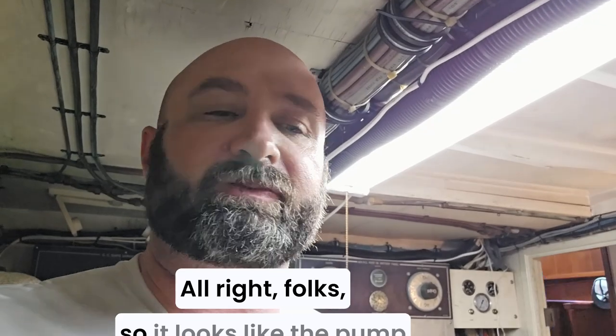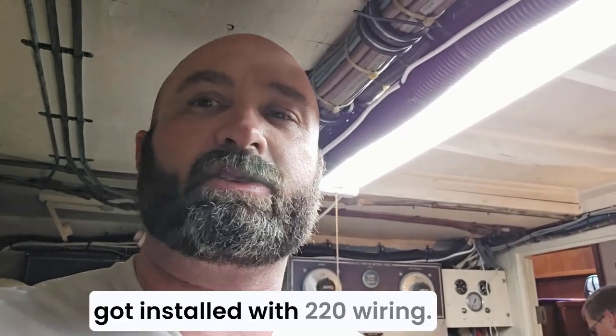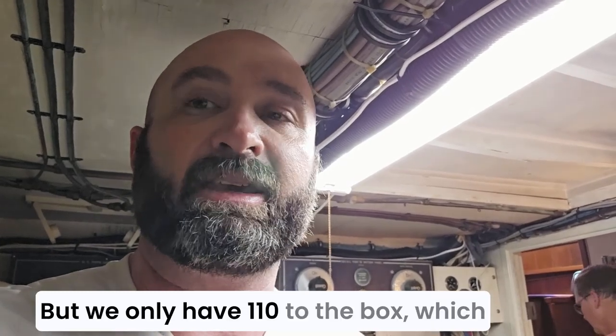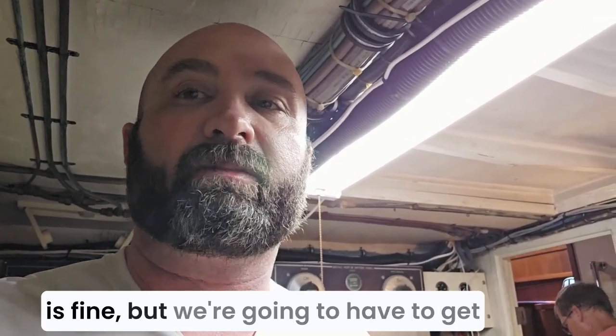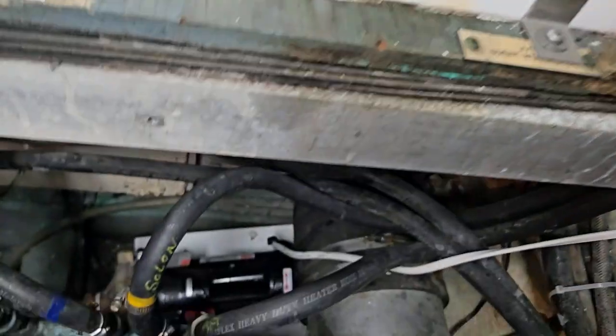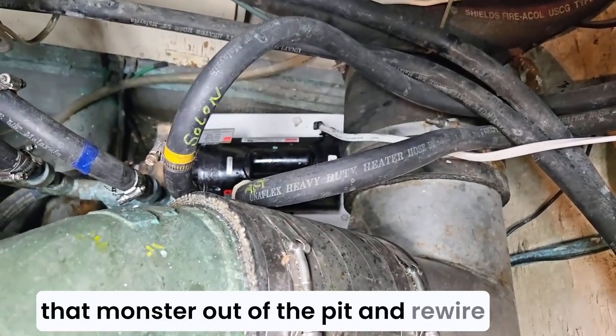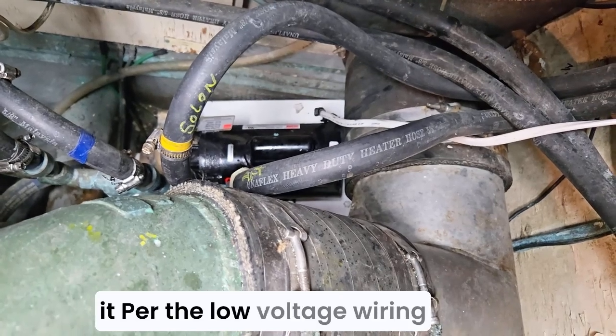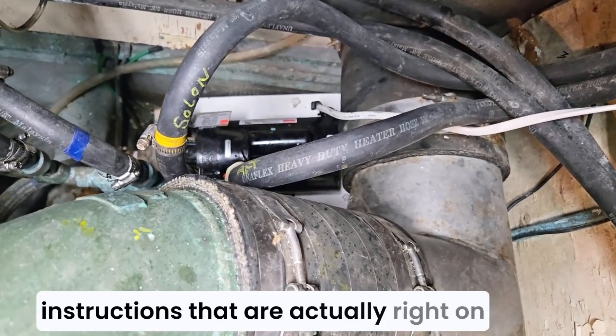Looks like the pump got installed with 220 wiring, but we only have 110 to the box, which is fine. But we're going to have to get that monster out of the pit and rewire it per the low voltage wiring instructions that are actually right on the case.